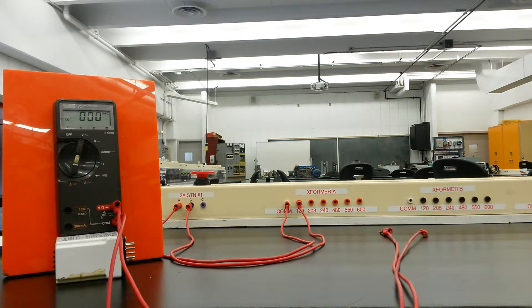So now that I've put this larger voltage across a smaller amount of turns, and I screwed up the connection, the 600 volts will now be 600 times root 3 or 1,038 volts. Okay, I would not suggest this whatsoever. I'm just showing you this in the shop just to show you what happens.